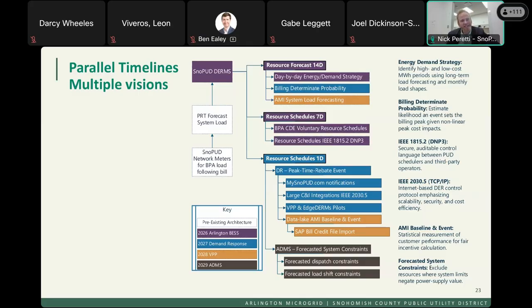They came back and said they wanted to do this proprietary OPC UA, since they'd already secured the contract and didn't want us to make them change their minds. We said, well, no, the contract for the service required an industry standard, not just a proprietary communications strategy. They were bummed out about it, but ultimately they read the contract and agreed we were right, that it's not an industry standard, and the only one we're aware of is 1815.2. So they ended up saying okay, that's our analysis too, and they went for it.